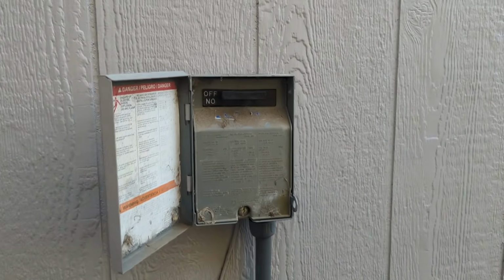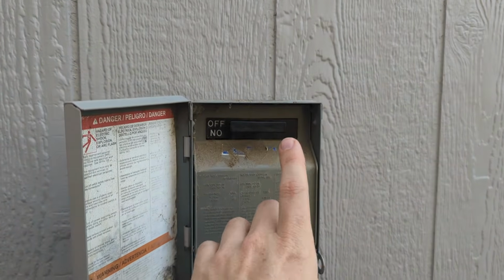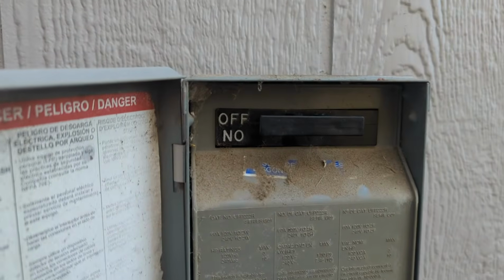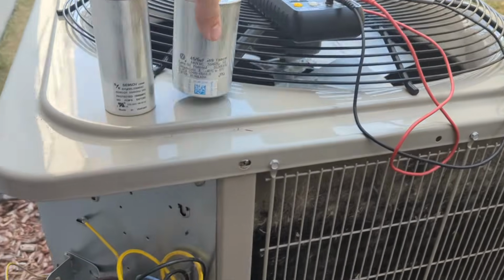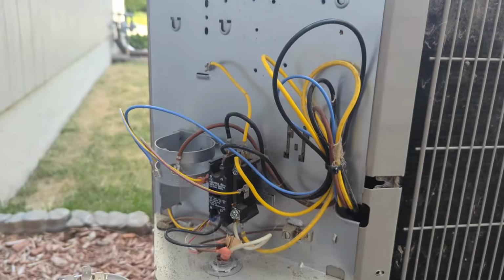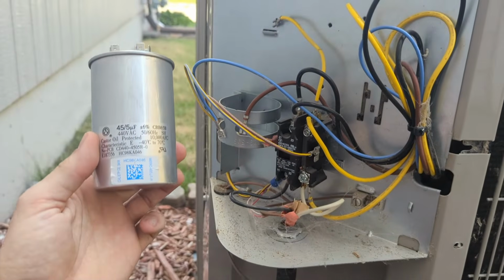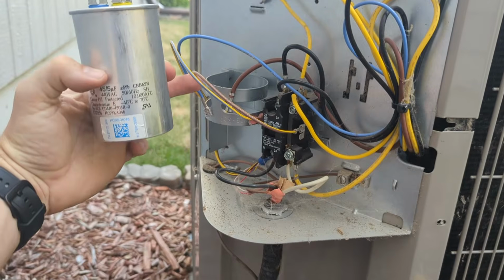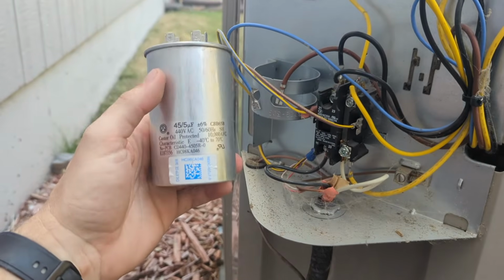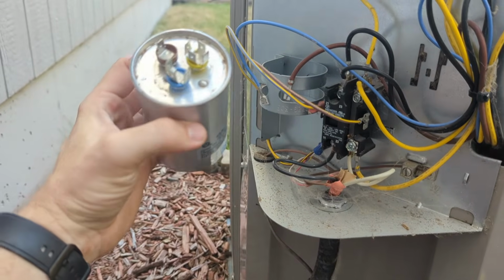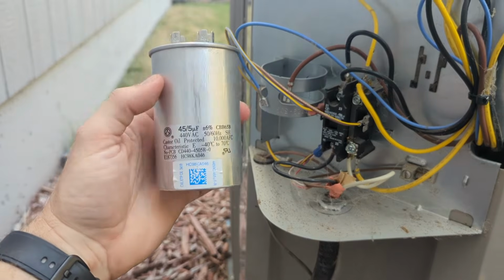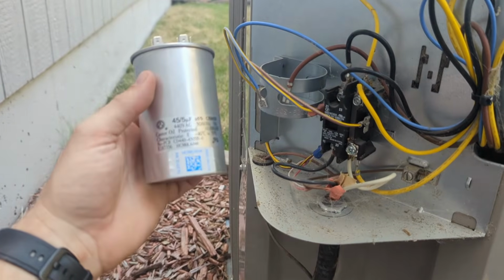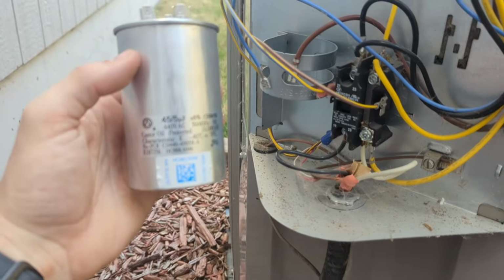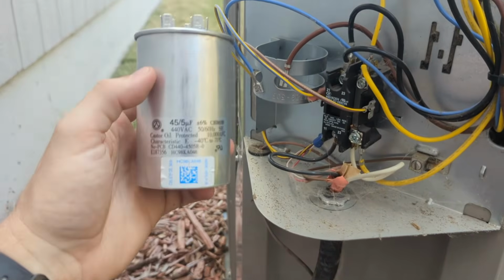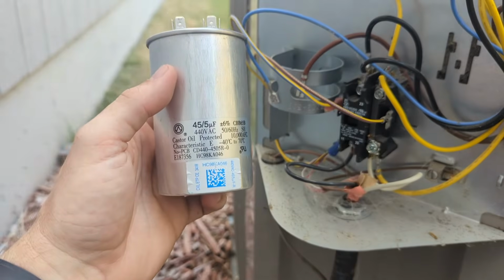As always, we want to make sure we've pulled out our disconnect and flipped it to off. This one is already done. Okay, we're going to come over here, and in the electric bay here, this is called a capacitor, and it was in this little sleeve right there, and it had some wires attached to the top. This is what allows the compressor and the fan to run. It provides a jolt of power when the system calls for cooling, and if it goes bad, your system just won't run. And this is probably the most common point.